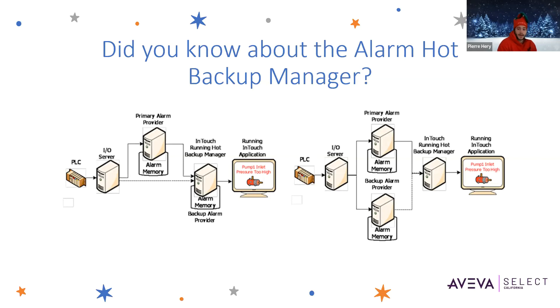The Hot Backup Manager synchronizes alarm acknowledgements between the primary and backup providers. So if you acknowledge the alarm on one, it'll be acknowledged on the other as well. The advantage to using the configuration on the right is that if the primary alarm provider fails, you have a backup one. The Alarm Consumer will still receive alarms from the backup, and will still reference the Hot Backup pair, so the backup provider will provide the alarm data at that point.